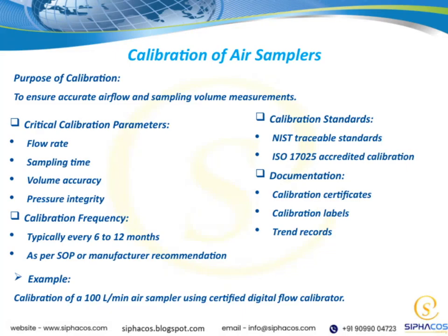Now, let's talk about calibration standards. It's essential to use NIST traceable standards to ensure our measurements are accurate and reliable. Additionally, calibration should be performed according to ISO 17025 accreditation, which guarantees that our calibration processes meet international quality standards.